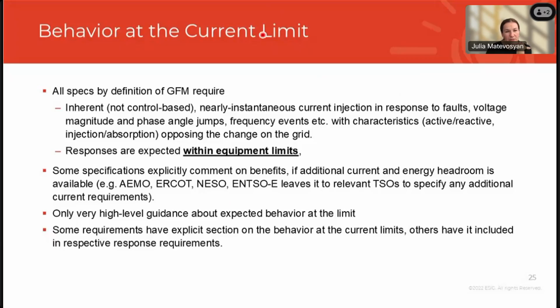Behavior at current limit. This is relatively common for all of the requirements. By definition, all of these requirements require grid forming to respond inherently and nearly instantaneously by injecting current in response to faults, voltage magnitude and phase angle jumps, and frequency events with different characteristics. So it's like active or reactive current injection or absorption, and it's supposed to oppose the change on the grid. And all of them say that responses are expected within equipment limits. Some specifications specifically comment that there is a benefit if there is additional overcurrent capability or energy headroom, and if it's available, it would be advantageous to use it, but it doesn't require oversizing resources.